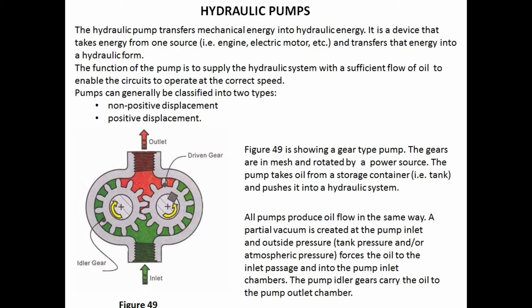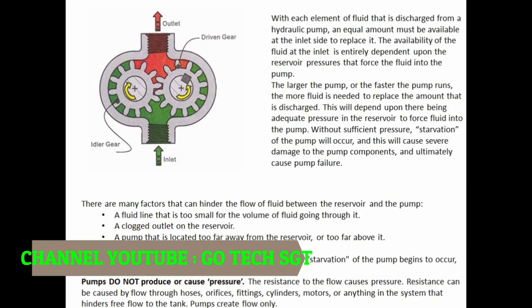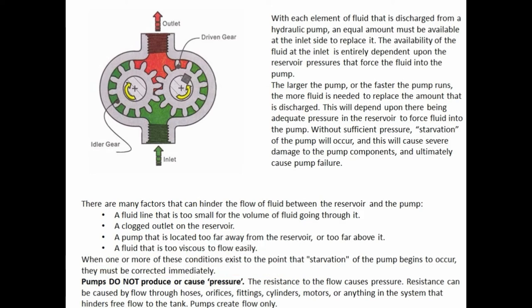The pump takes oil from a storage container (tank) and pushes it into a hydraulic system. All pumps produce oil flow in the same way: a partial vacuum is created at the pump inlet, and outside pressure (tank pressure and/or atmospheric pressure) forces the oil to the inlet passage and into the pump. With each element of fluid discharged from a hydraulic pump, an equal amount must be available at the inlet side to replace it. The availability of fluid at the inlet depends entirely upon reservoir pressure. The larger or faster the pump runs, the more fluid is needed; without sufficient pressure, starvation of the pump will occur.